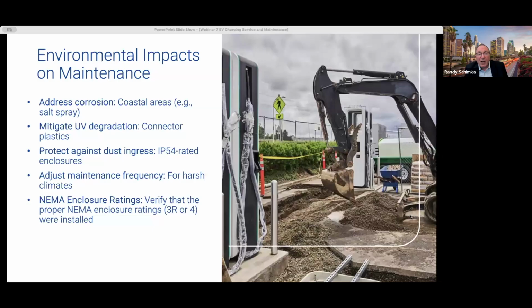For protecting against dust getting into the charging station, ensure that chargers and enclosures have ingress protection ratings of IP54 or higher. This will help to keep dust out, but you'll still need to clean filters and seals to prevent any buildup that could affect performance. You may need to adjust maintenance frequency for harsh climates like extreme heat or cold or humidity. Increase inspections in tough conditions to catch wear or any other issues early and avoid downtime.